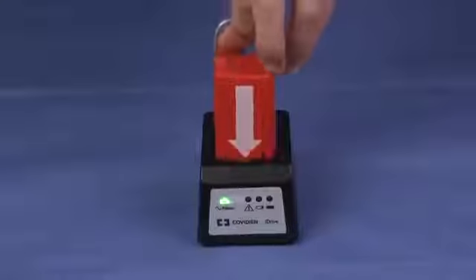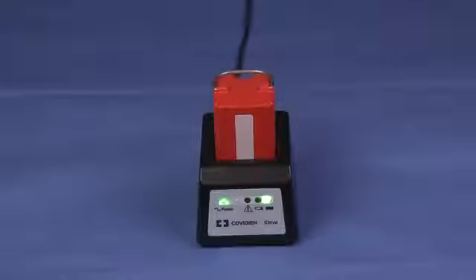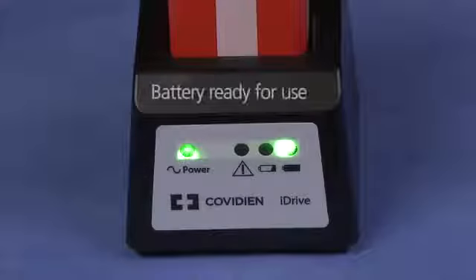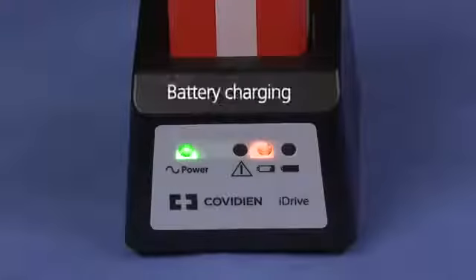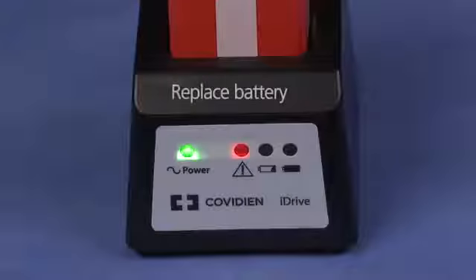Confirm that the iDrive battery pack is sufficiently charged using the status indicator lights on the iDrive battery charger. The battery charger will show 2 solid green lights to indicate the battery is sufficiently charged. When the battery is charging, the battery charger will show a flashing amber light in addition to the solid green power indicator light. Do not use the battery until 2 green lights are shown on the battery charger. A red indicator light on the battery charger indicates that the battery has reached the end of its service life or otherwise should be replaced.